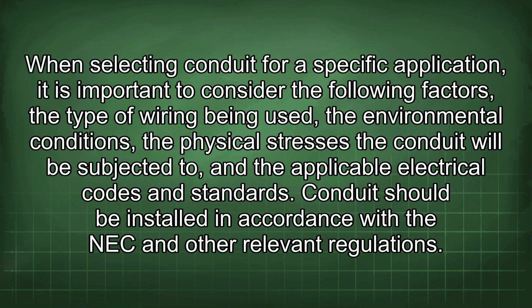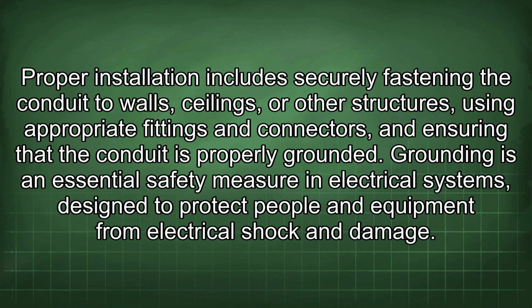When selecting conduit for a specific application, it is important to consider the following factors: the type of wiring being used, the environmental conditions, the physical stresses the conduit will be subjected to, and the applicable electrical codes and standards. Conduit should be installed in accordance with the NEC and other relevant regulations. Proper installation includes securely fastening the conduit to walls, ceilings, or other structures, using appropriate fittings and connectors, and ensuring that the conduit is properly grounded.